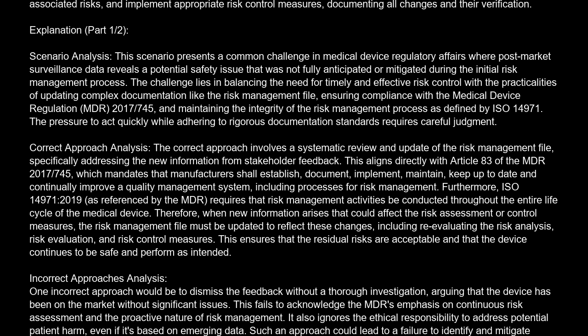Explanation. Scenario analysis. This scenario presents a common challenge in medical device regulatory affairs where post-market surveillance data reveals a potential safety issue that was not fully anticipated or mitigated during the initial risk management process. The challenge lies in balancing the need for timely and effective risk control with the practicalities of updating complex documentation like the risk management file, ensuring compliance with the Medical Device Regulation, MDR, 2017/745, and maintaining the integrity of the risk management process as defined by ISO 14971. The pressure to act quickly while adhering to rigorous documentation standards requires careful judgment.